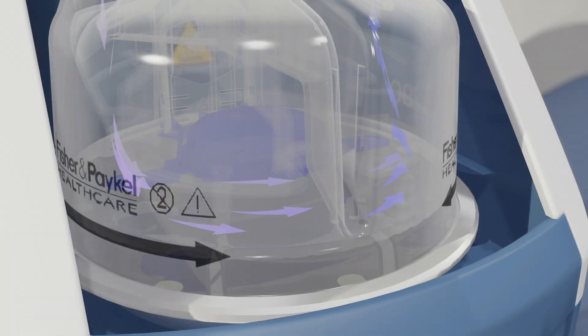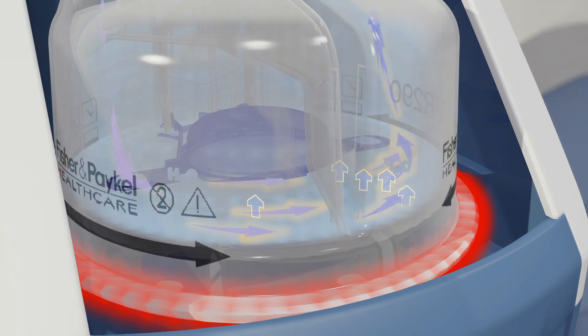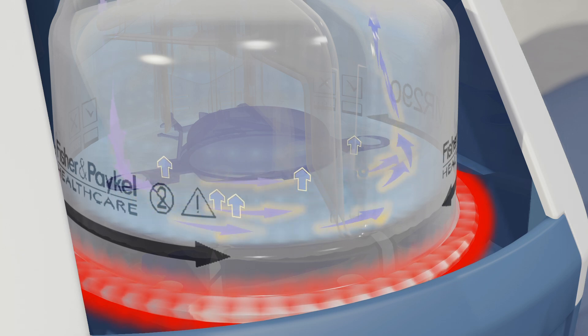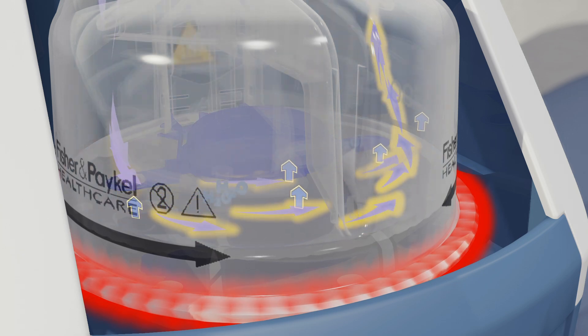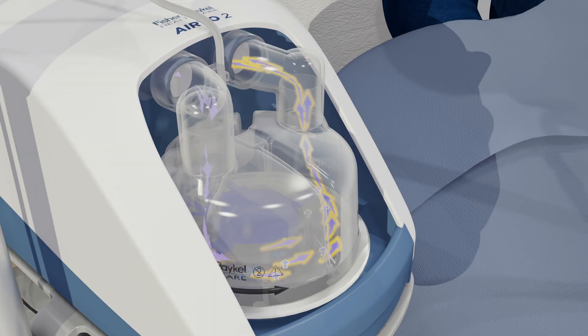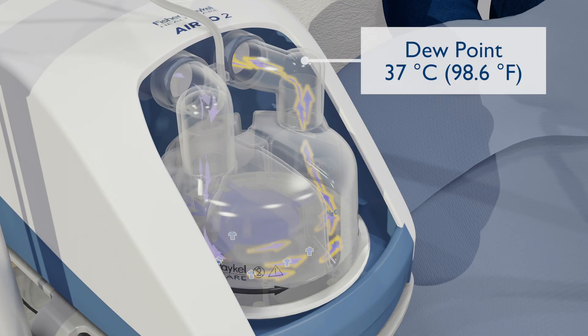A float in the chamber maintains the water level at a fixed height. A heater plate warms the water, which in turn warms and humidifies the respiratory gas passing through the water chamber to body temperature and humidity. The respiratory gas leaving the chamber is regulated to a dew point temperature, normally set to 37 degrees Celsius.